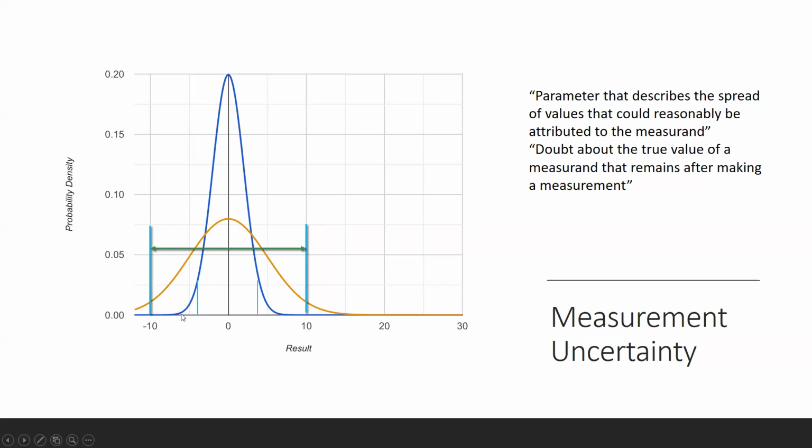And you could multiply the standard deviation by a fixed number to give you a 95% confidence interval again, for example. Now, bias isn't included in this calculation, as the thought process is that calculated bias should be either minimized or corrected for. But how you've decided to minimize or correct for your bias would come with an imprecision, which would be included in this.